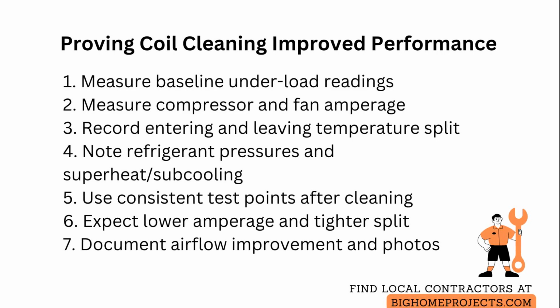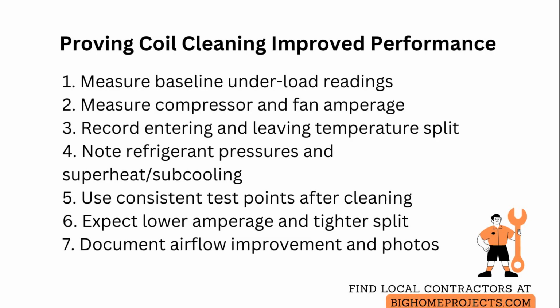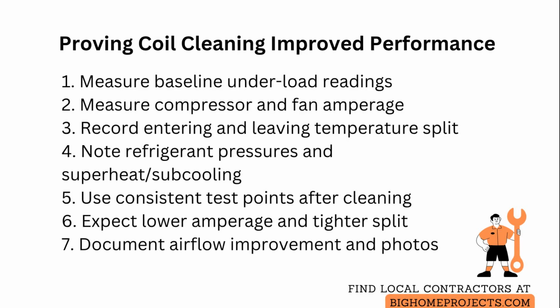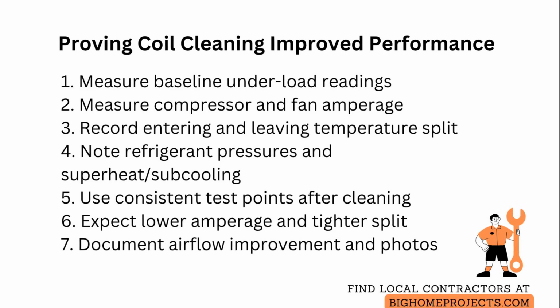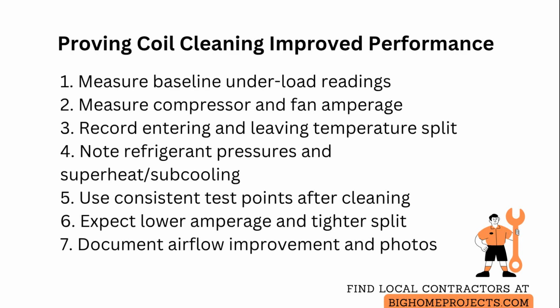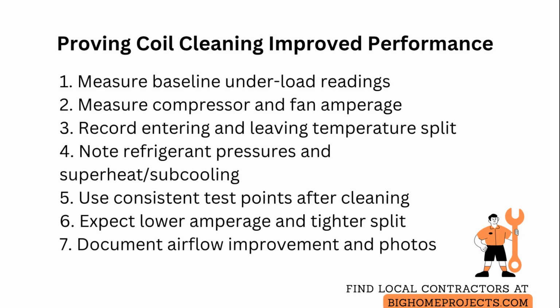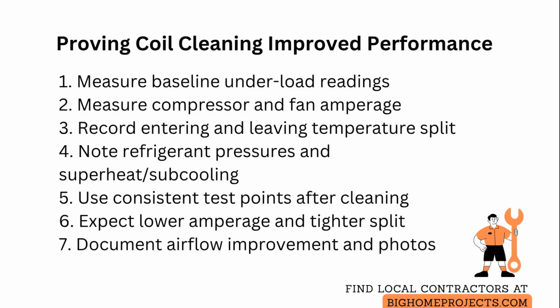Expect to see lower motor amperage, a tighter temperature split that matches manufacturer specifications, and refrigerant property shifts toward expected superheat or subcooling ranges, indicating the heat transfer surface is restored. If safe and needed, document airflow improvement by simple methods like static pressure or a consistent hand test near return and supply registers, and photograph or log readings for your service record.